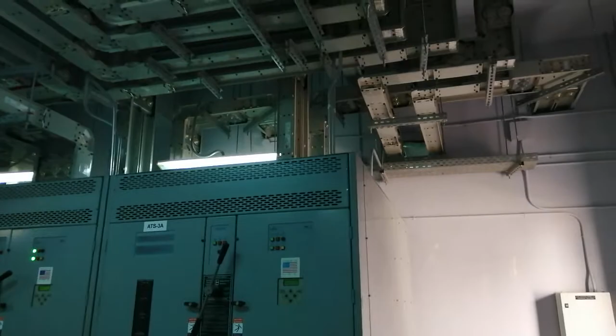And then from ATS to synchronization, and then from synchronization, and then from ATS to MDB. Like this, we have connection, all connection by busway. See? No cable. This is ATS. And this is MDB. Busway. Some cable output, meaning from MDB output we have also busway and also cable, but maximum work is busway. Yeah, 90%, 95%.